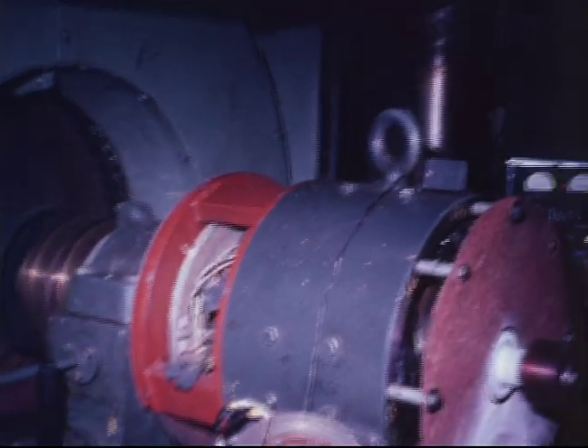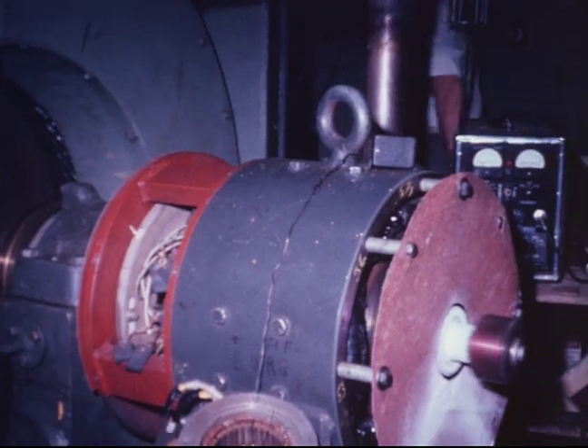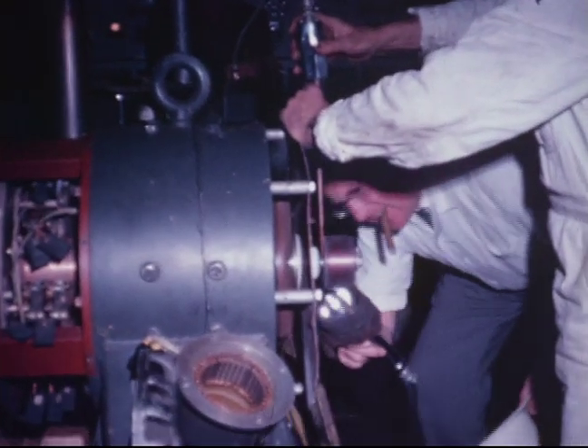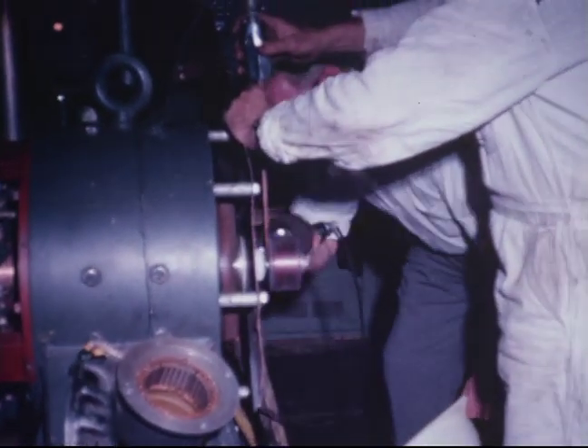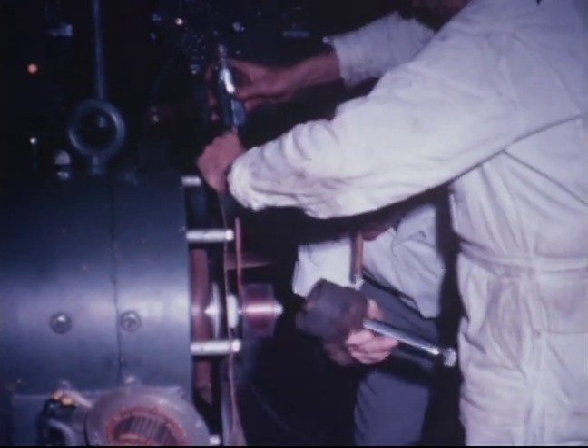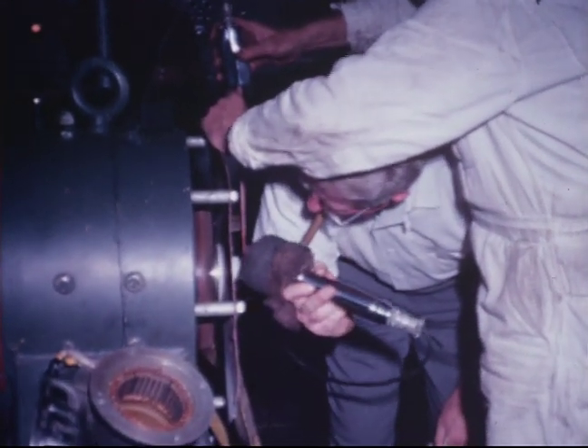During initial runs, generator number 1 vibrated excessively because of misalignment of the rotor. It was removed, reworked, balanced, and reinstalled. The engineer with the strobe light is making dynamic balancing tests.